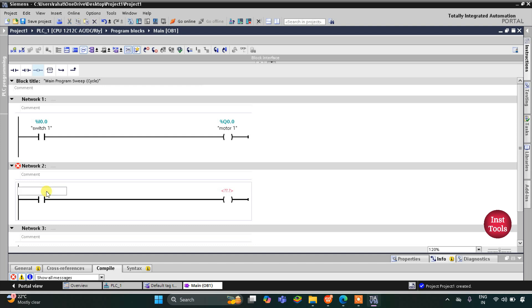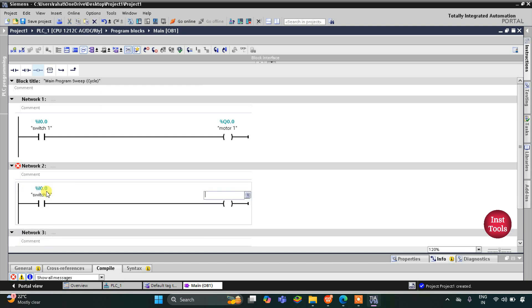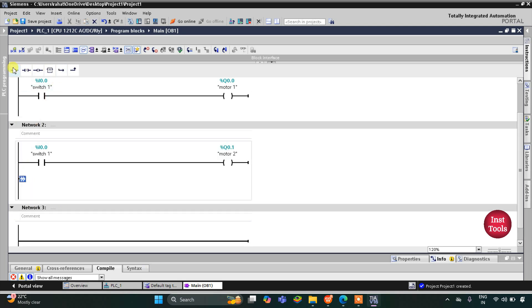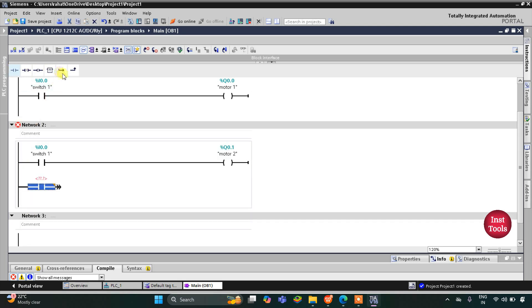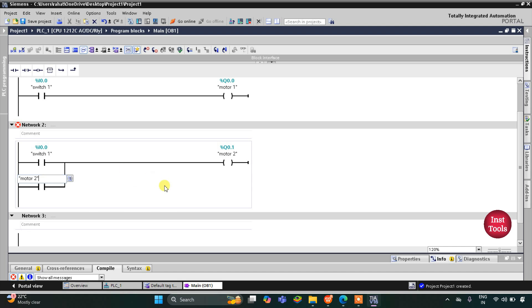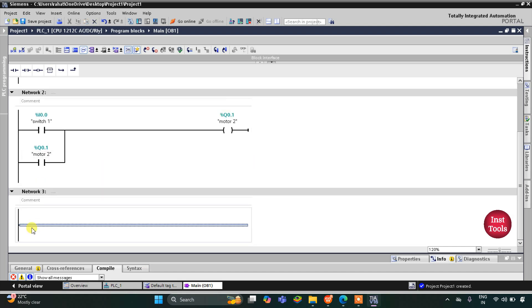This will be switch 1 and then it will be motor 2. But motor 2 should remain on when switch 1 is turned off, so for that we will implement latching. I will open a branch and then add one normally open contact and close it — this will be motor 2. So motor 2 is now latched.